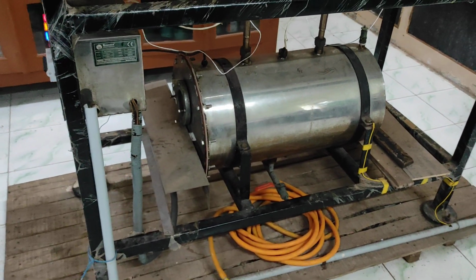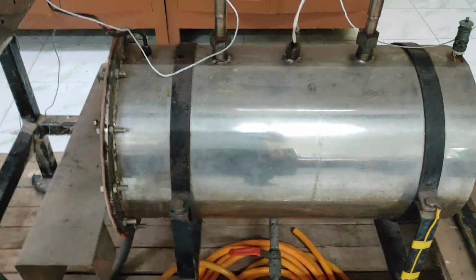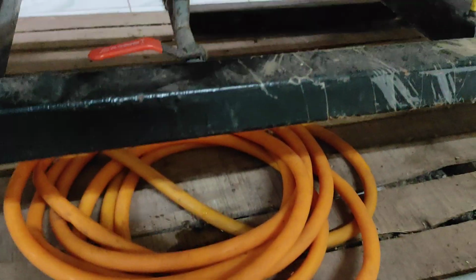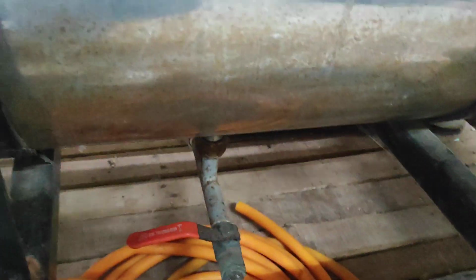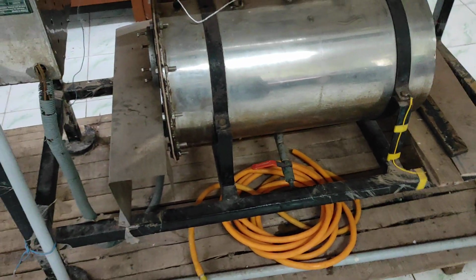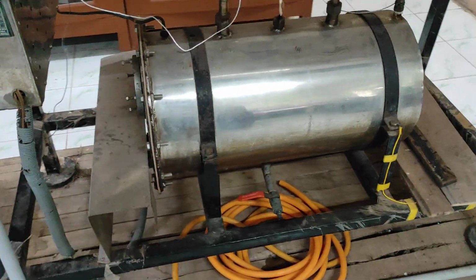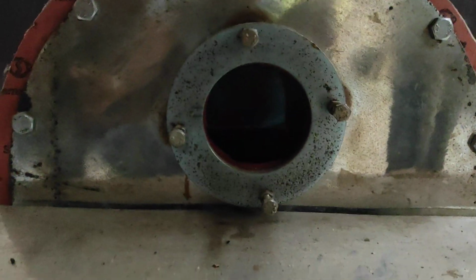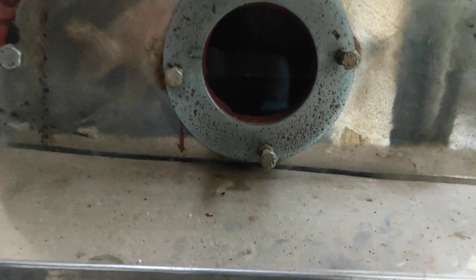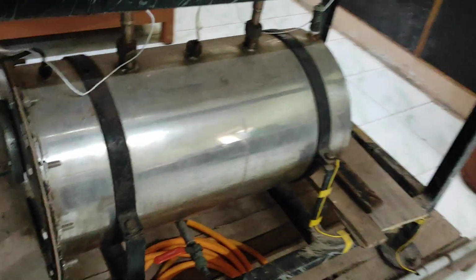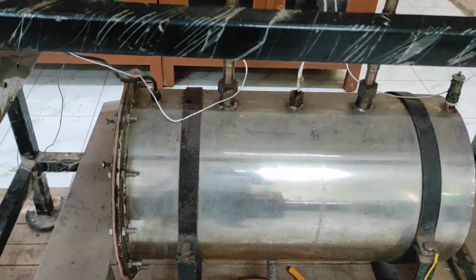So this autoclave has only two parts. This is called the boiler, and we fill water through this. Generally we fill deionized water or distilled water, but since it is expensive, we are using RO water here. Then we can check the level of water availability. This is a glass, so here we can check how much water is there, and we can adjust the minimum requirement level. In the boiler there are electric heating rods, connected with the power supply.